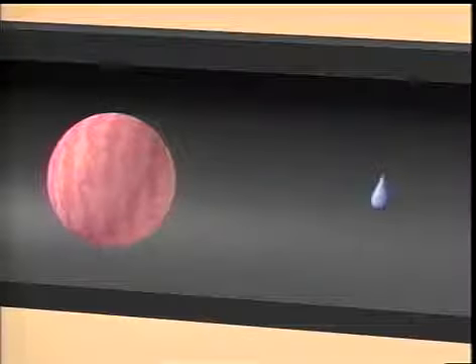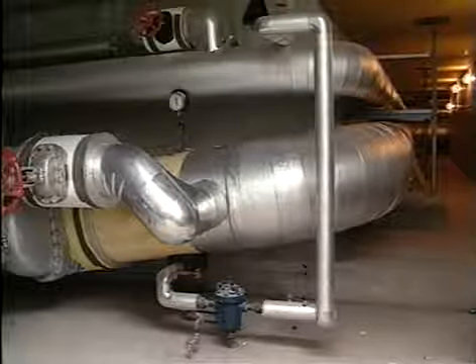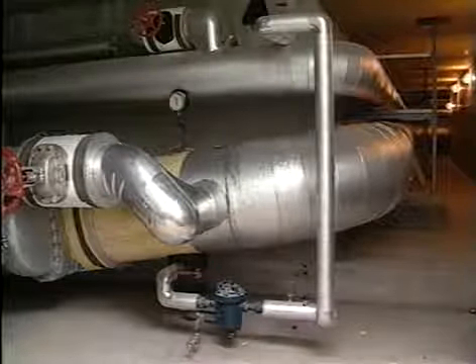Water hammer may also be initiated by thermal shock. In biphase systems, steam bubbles may become trapped in pools of condensate. Since the condensate temperature is usually below saturation, the steam will immediately collapse. Steam occupies hundreds of times the volume of an equal amount of water. When the steam collapses, water is accelerated into the resulting vacuum from all directions. When the void is filled, the water impacts at the center, sending shock waves in all directions. One likely place for thermal shock to occur is in steam utility corridors.